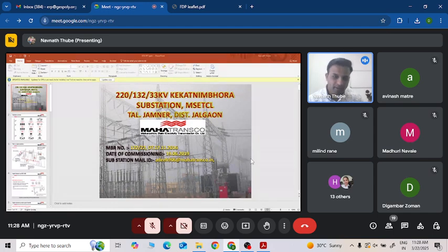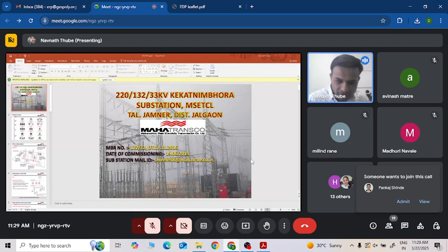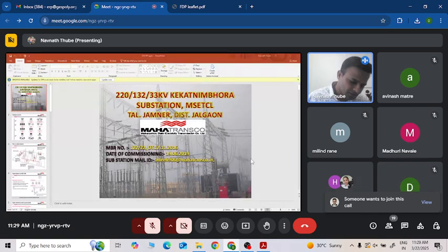Normally, our conventional substation includes an EHV switchyard having various EHV equipment like CT, PT, breaker, then transformer, and all the cabling work, cable trenches. Each equipment has its own individual marshalling box, and from the marshalling box the cable work goes to the control room. In the control room there are various control and relay panels equipped with relays and meters. The CTs and PTs, which are EHV substation equipment, measure our day-to-day hourly readings, and that is transferred to our control and relay panels through regular copper cables via the MB, and reported to the SCADA as well as the relays and meters.